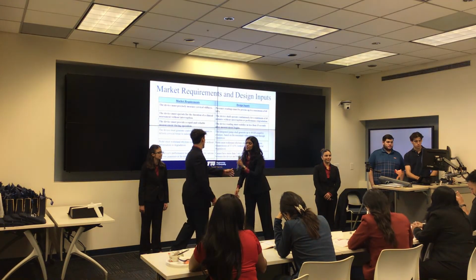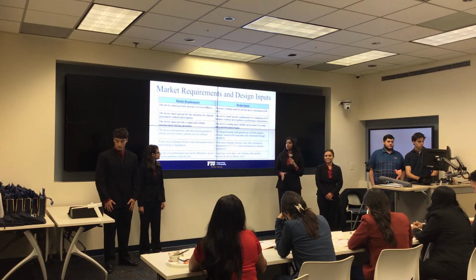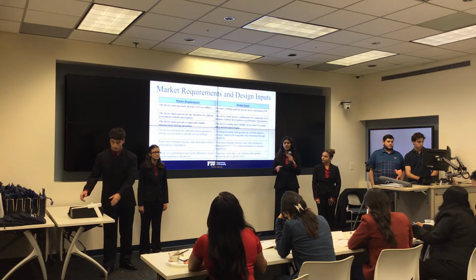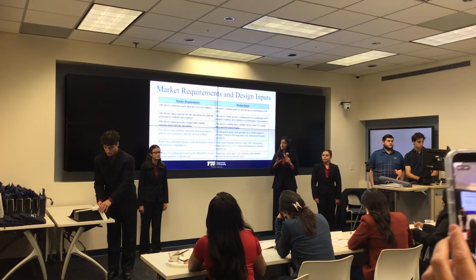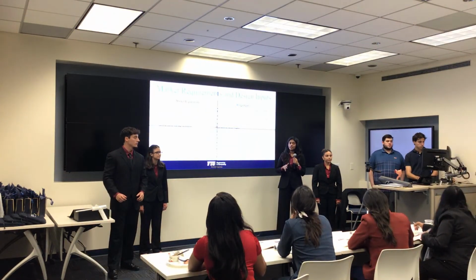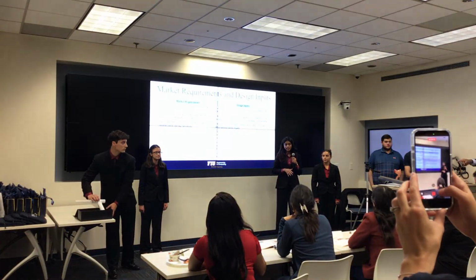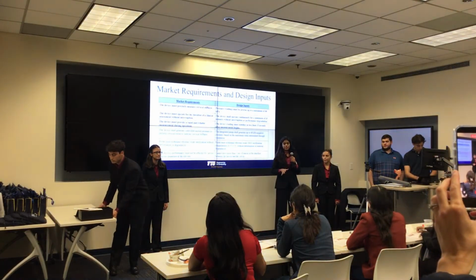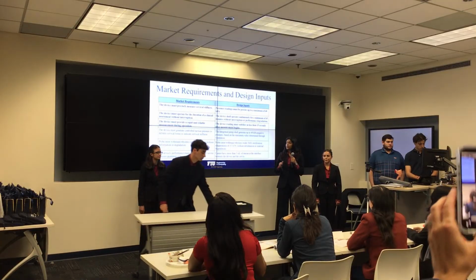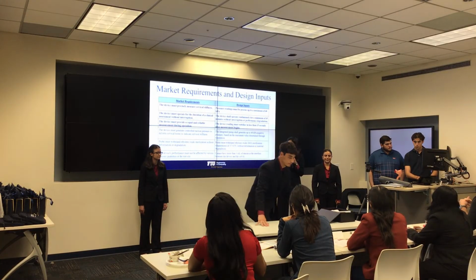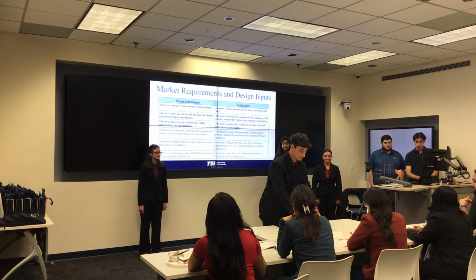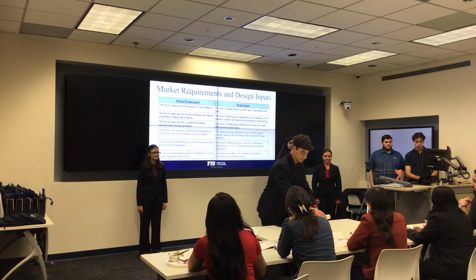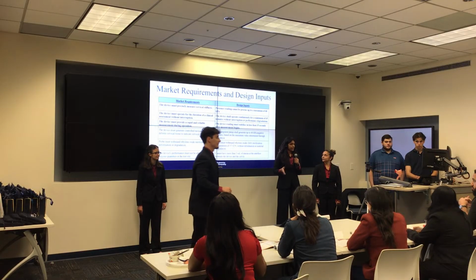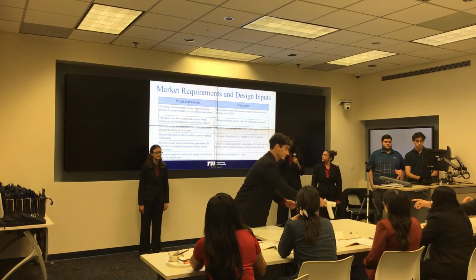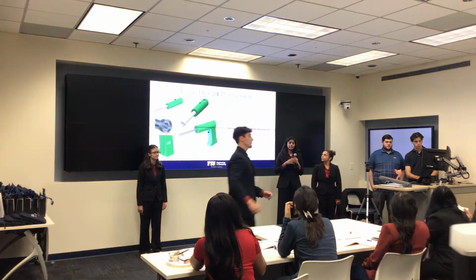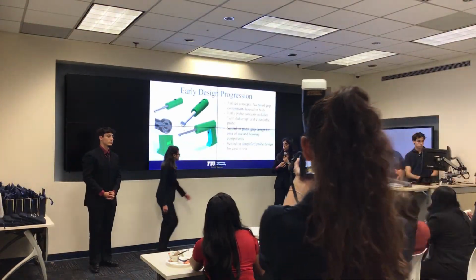Thank you, Andres. So for our market requirements and design inputs, we focused on making our device both reliable and easy to use in a clinical setting. Some of the key requirements that we identified for our device was that it must be able to precisely measure the cervical stiffness with pressure readings up to 40 kPa. It also must be able to run for at least 45 minutes without degradation and give a stable reading within 15 seconds of operation. Some of the other factors that we also looked at were sterilization, ergonomics, and continuous running during different conditions. Now I'm going to pass on to Natalie to talk about the design progression.